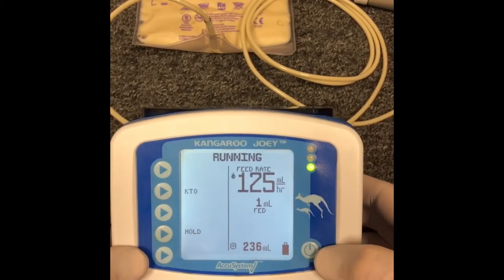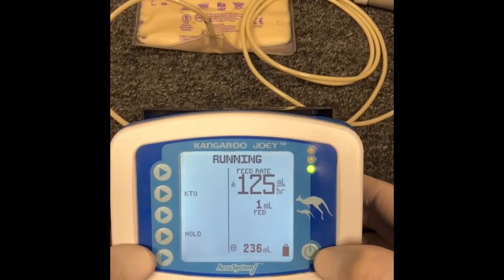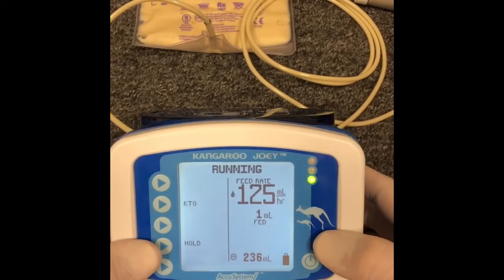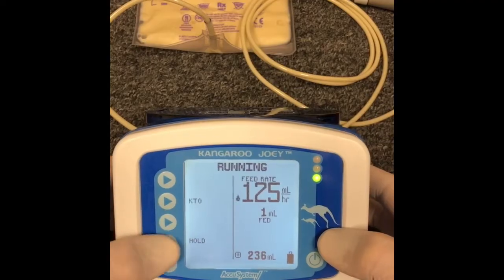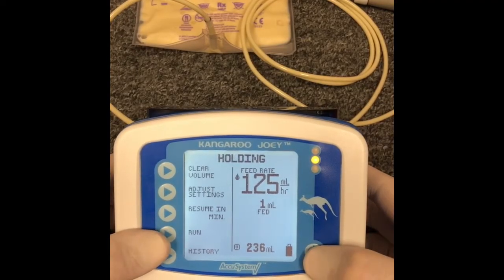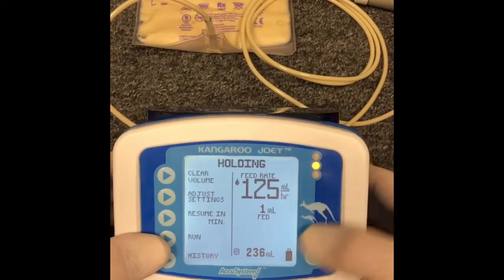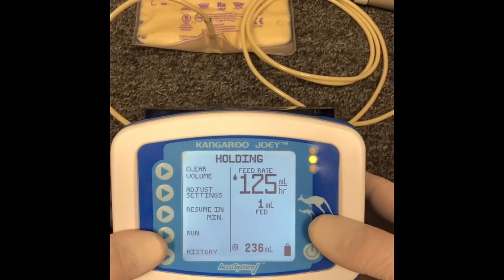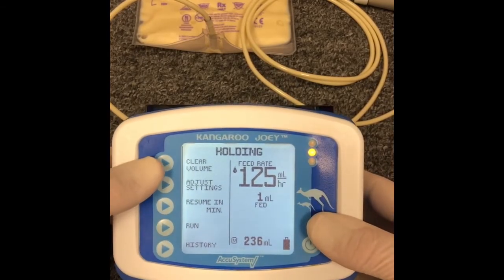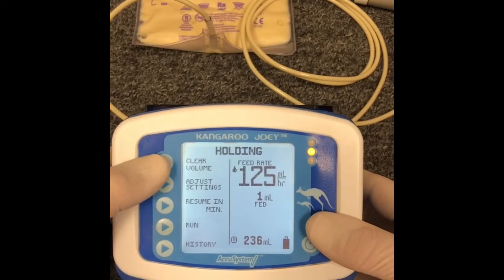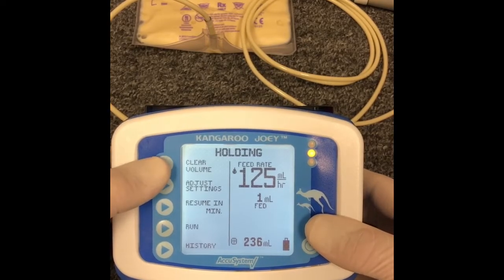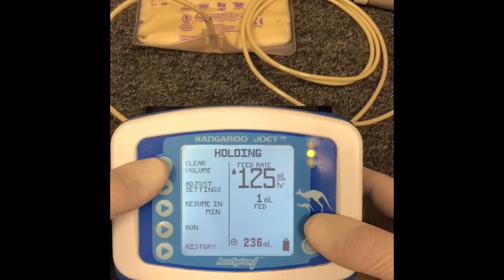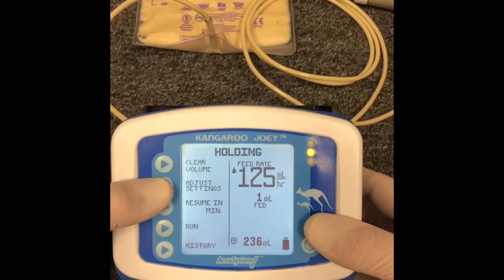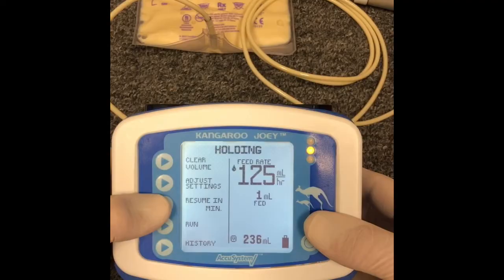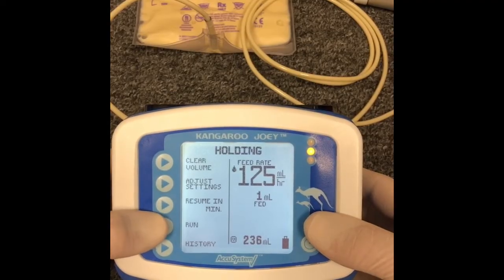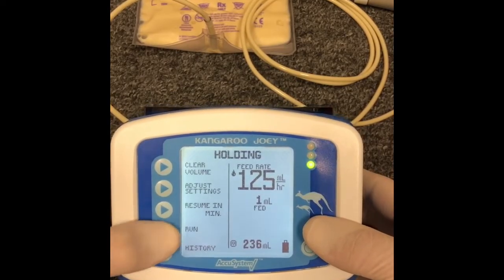Important thing to note is if the patient needs to stop this pump at any time, if they need to pause it, take a shower, do whatever, they can stop it, they can turn it off. When they turn it back on, it's going to remember exactly where it was at, and it'll pick up right where it left off. As you can see here, once we pause it, it has a few different options. It has a clear volume, which is clearing out the volume to start the feeding over again, if you say, hey, I want to start my feeding over again right now. Adjust settings if you want to change those settings around. Resume in 1 minute, or run it again. Don't worry about history. So go ahead and run it again.